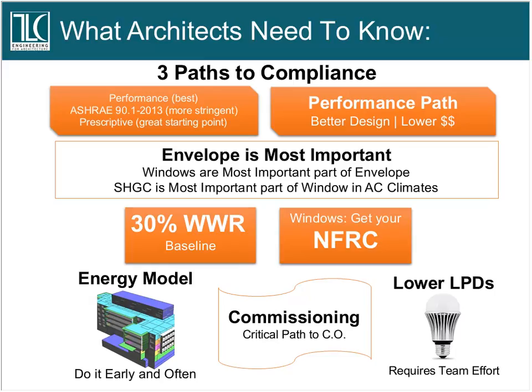Commissioning is now a code requirement on lighting controls for all projects and for HVAC systems on relatively modest-sized projects and larger. This used to be something that we just did on LEED projects. It's now part of the basic building energy code and can be a really important element because it's now on the critical path to your certificate of occupancy. And then finally, we're going to talk about the lower lighting power densities. That's what LPD stands for, the lower amount of electrical energy that you can spend on lighting. And in order to do that, it really requires, once again, a team effort. So there's a theme here. The theme is it takes teamwork to deliver one of these projects in the new energy code.